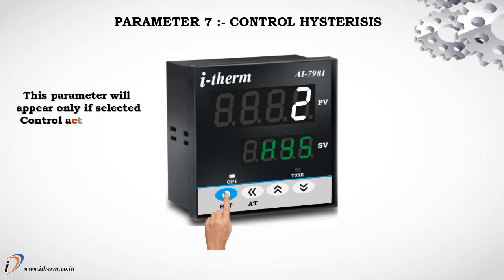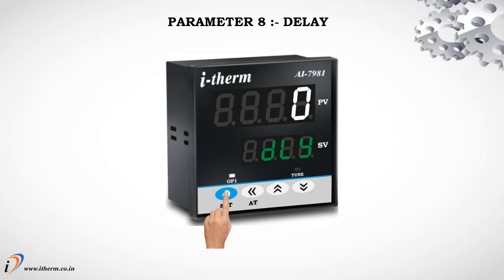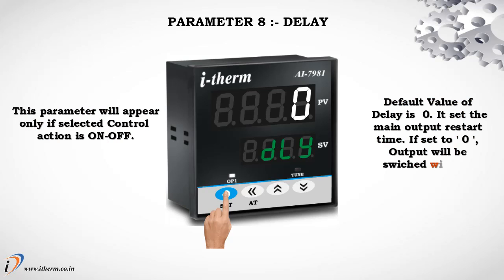Parameter 7: Control Hysteresis. This parameter will appear only if selected control action is on-off. Default value of hysteresis is 2 degrees centigrade. It sets the dead band between on and off switching of the output. Parameter 8: Delay. This parameter will appear only if selected control action is on-off. Default value of delay is 0. It sets the main output restart time; if set to 0, output will be switched without delay.